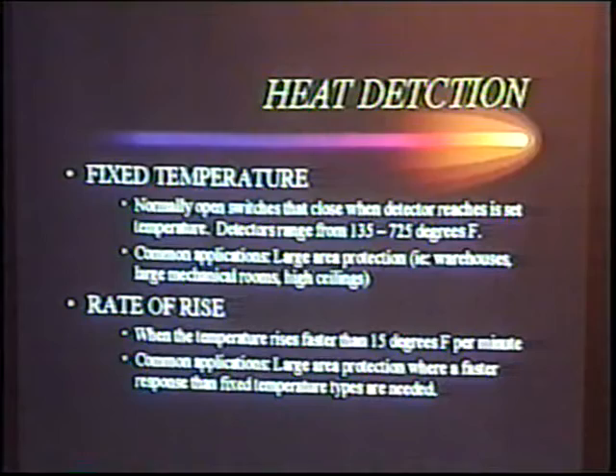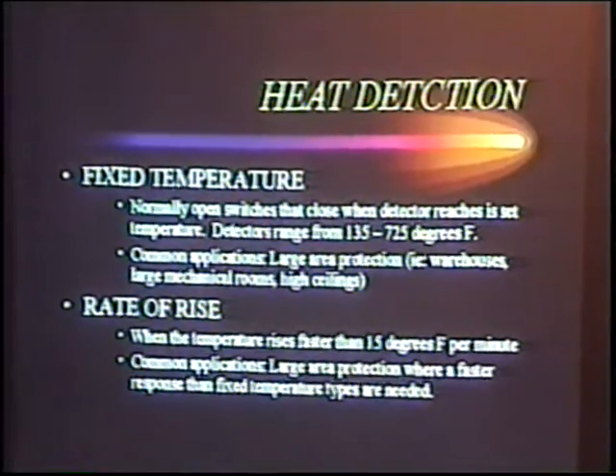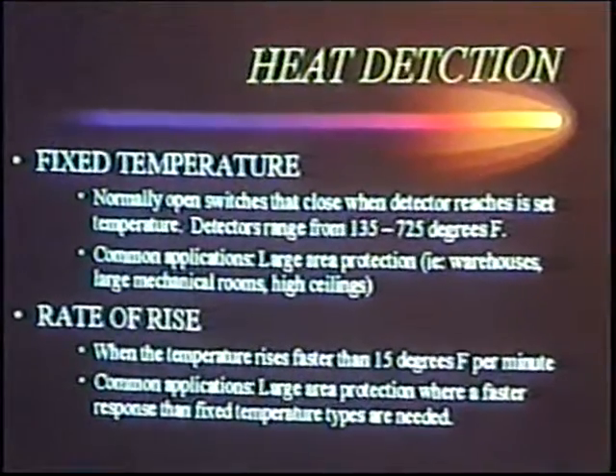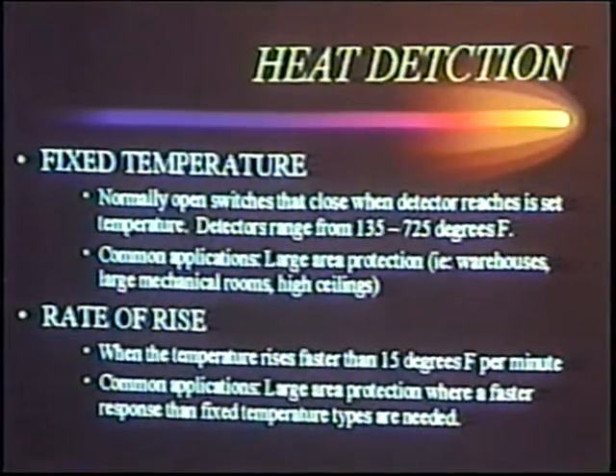Getting towards the end of this fourth stage of the fire, the heat stage, I believe we have three different types of heat detectors: the most common, fixed temperature, rate of rise, and linear heat detection, which we'll get to. What's a fixed temperature detector? It's a normally open switch that closes when the detector reaches its set temperature. Typically, the detectors we use range between 135 and 725 degrees. There are special heat detectors that go much higher than that, for very specific applications.